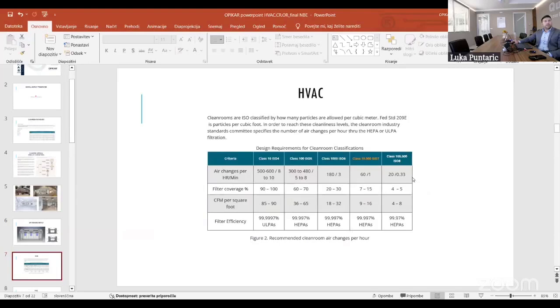So if I go on, HVAC. Previously we had a table of particles shown in different ISO classes in a cubic meter. Here, a very important figure that needs to be taken into account is the air change rate, which refers to the whole volume of the room. Here we have it for different classes. Completely to the right, ISO 8 class means 20 air change rates, then ISO 7 60 rates, ISO 6 180 rates, ISO 5 300 to 480 rates, and ISO 4 500 to 600 rates.